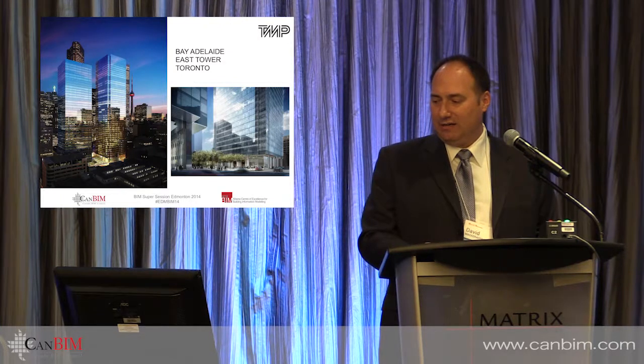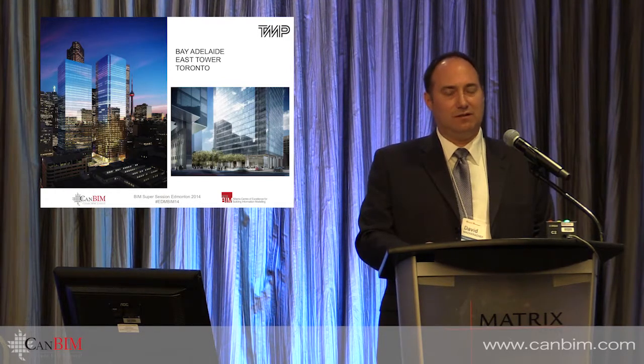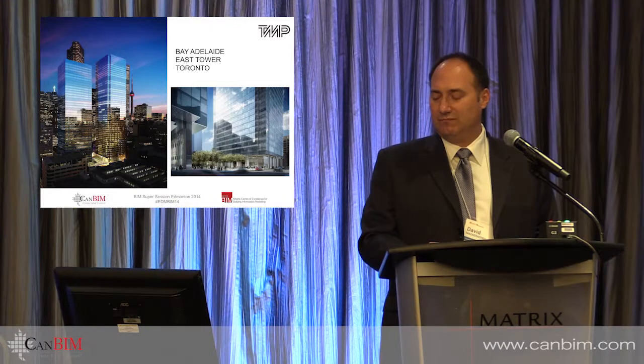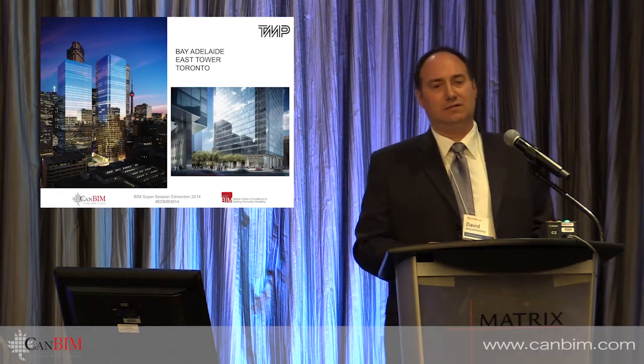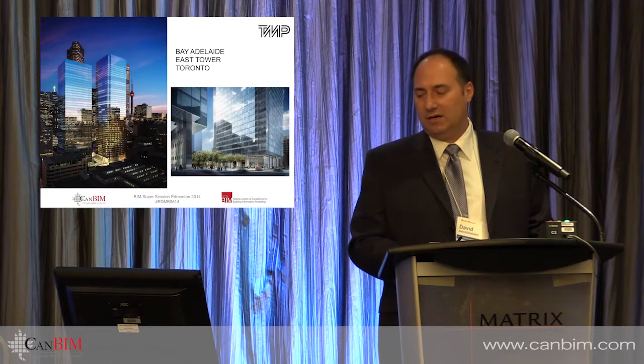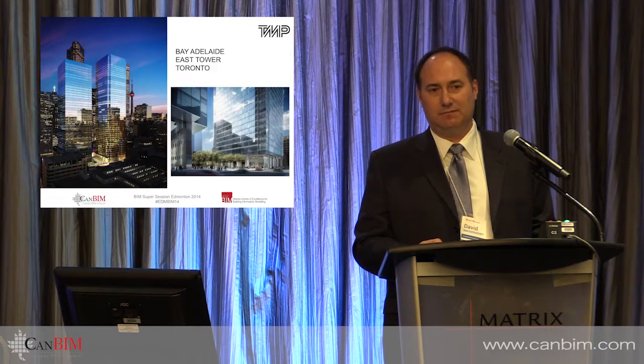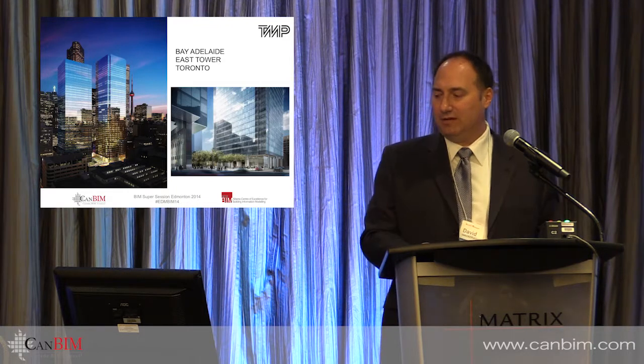So in the case of Bay Adelaide, what happened was they took that and they redrew it, but they didn't necessarily follow our drawings. They drew it themselves the way they thought it was going to fit and the way that they thought it was going to better serve their purposes, because they cut out some sheet metal fittings, they cut out some pipe fittings, and there was what they thought was going to be some increases in efficiencies on their side. And what it ended up doing was messing up a whole bunch of the coordination that had been done in the design model between us and the structural engineers on the job. So by not following our model, they ended up creating more havoc for themselves than they'd ever imagined. That's just something for all of us to consider when we talk about how that model transitions.